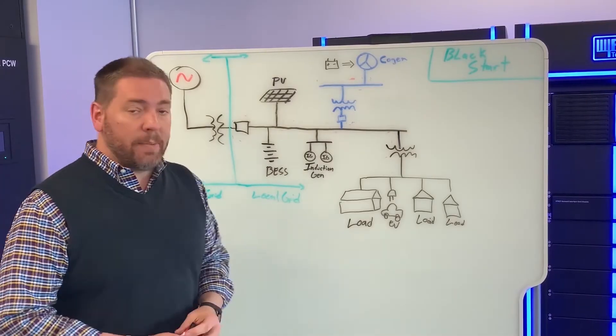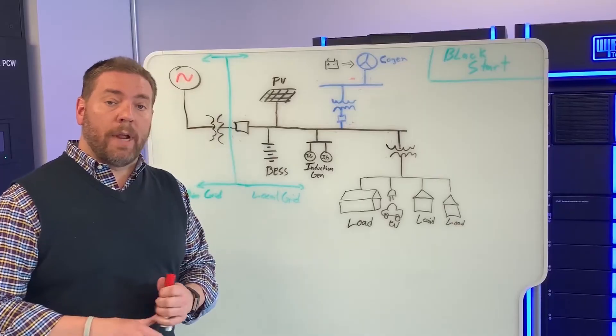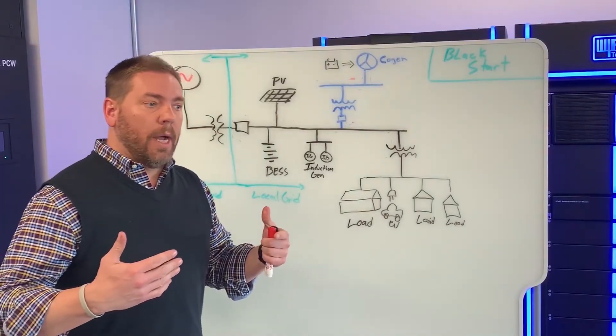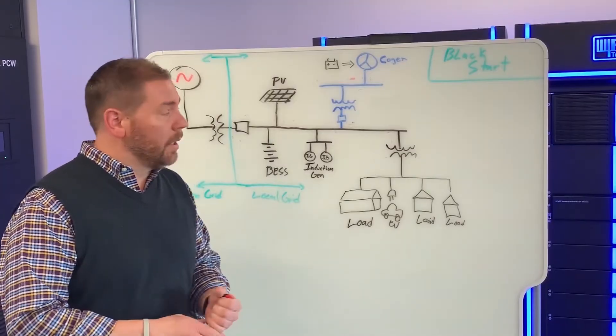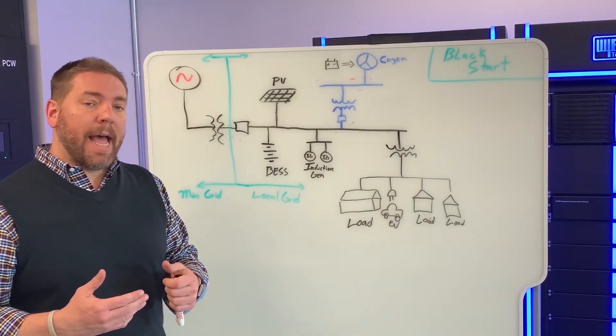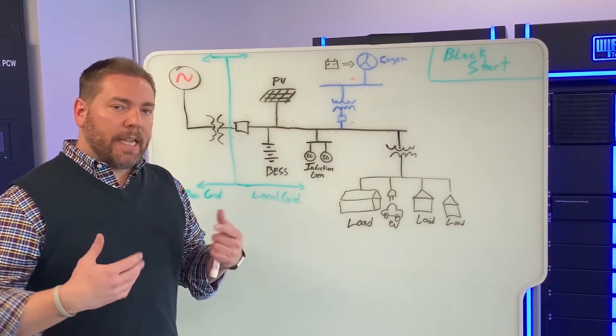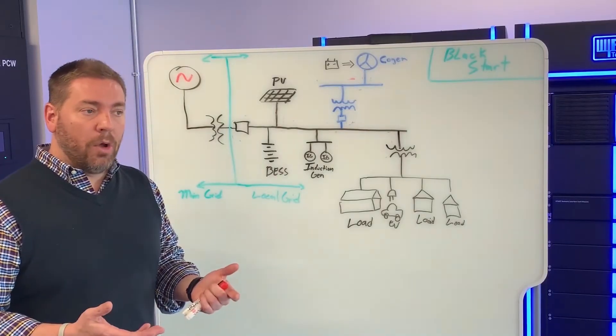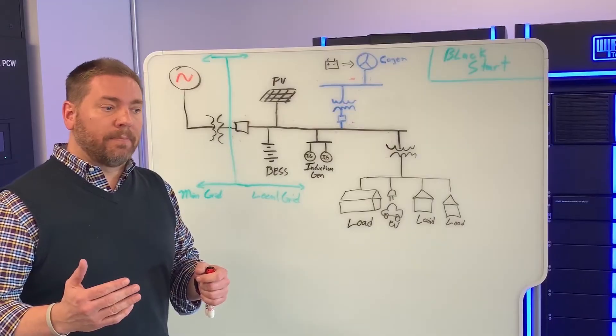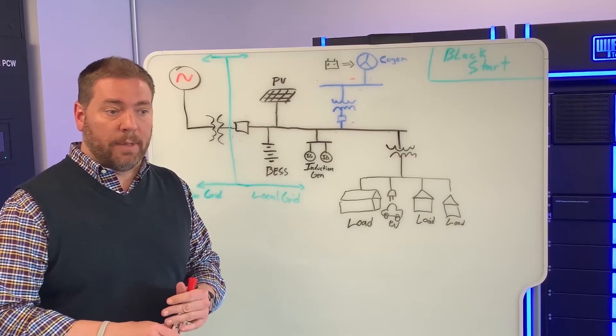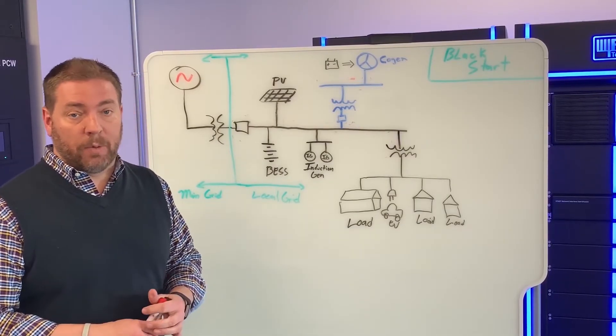First of all, the DER needs to be able to start its own ancillary services or internal process so they can start outputting power. And second is once it has started that service and is able to connect to the grid and take it on load, it needs to be able to control so that those loads do not bring the voltage or frequency down to a value that the system would collapse.